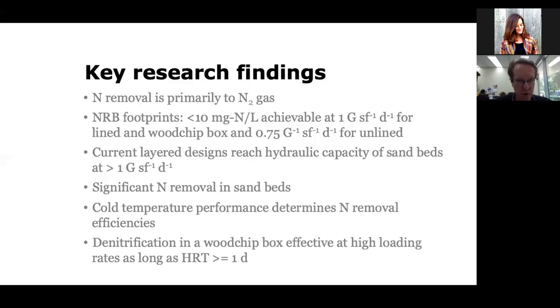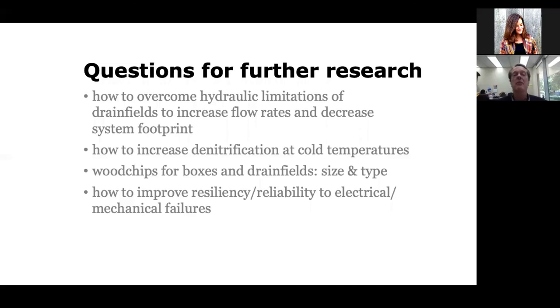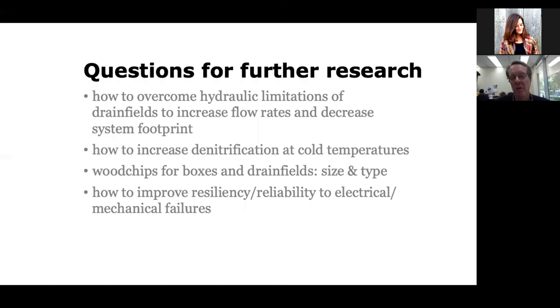Our key research findings: NRBs remove nitrogen to N2 gas, with no evidence yet of significant intermediate production of potential greenhouse gases. For lined and wood chip box systems, a year and a half of evidence shows you can load them at one gallon per square foot per day and achieve under 10 milligrams of nitrogen per liter in final effluent. For unlined systems, you load at 0.75 gallons per square foot per day. With current layered designs, they reach hydraulic capacity above one gallon per square foot per day. We get significant nitrogen removal in sand beds — about a third — and the key to optimizing these systems further is designing them to perform better in cold temperatures, which remains a challenge we're working on.